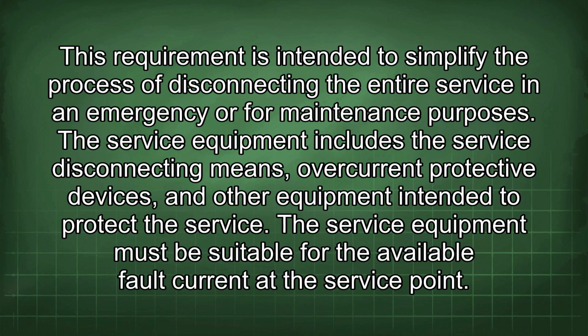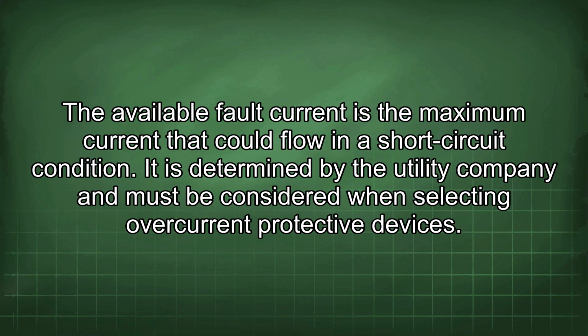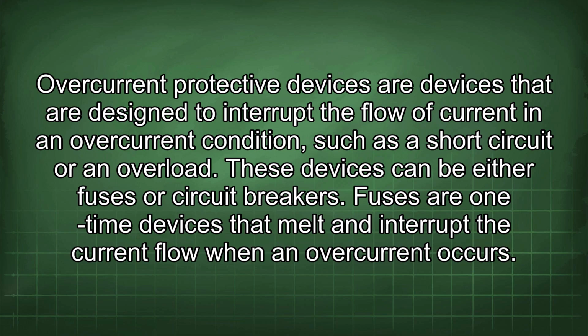The service equipment must be suitable for the available fault current at the service point. The available fault current is the maximum current that could flow in a short circuit condition. It is determined by the utility company and must be considered when selecting overcurrent protective devices. Overcurrent protective devices are devices that are designed to interrupt the flow of current in an overcurrent condition such as a short circuit or an overload. These devices can be either fuses or circuit breakers.